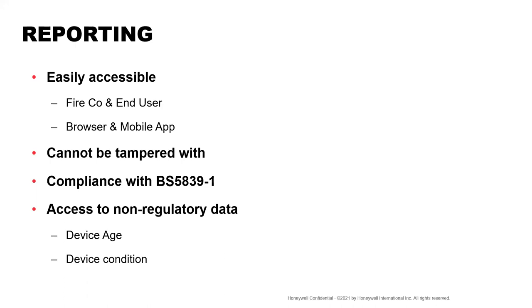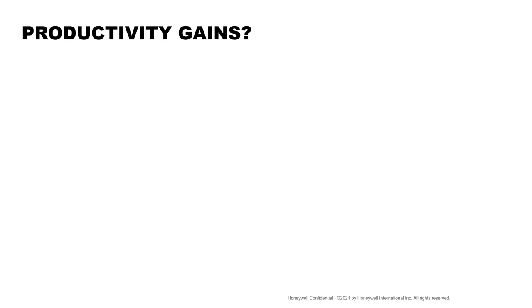Description of potential false alarm conditions as well, and device replacement ID. That's important because as buildings change internally, you might change the type of device. So if a particular room in a building has gone from being an office where it had a smoke detector, and that office has now been converted and is now a kitchen, you'd probably put a multi-sensor in there rather than just a smoke detector, because smoke detectors in kitchens inevitably are going to go off all the time. So you'd probably put a heat detector. So it should be able to tell you the device replacement ID, what's been changed. And obviously, once again, it'll all be recorded on the logs and the history.